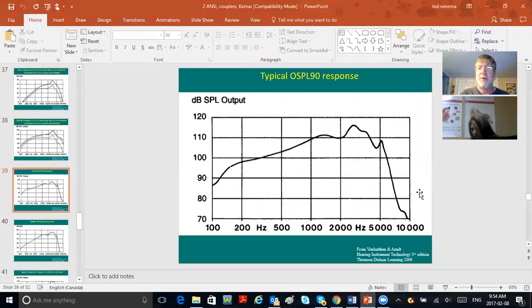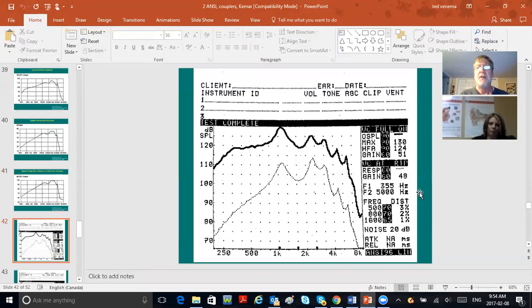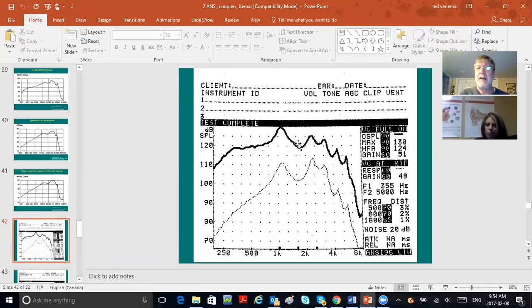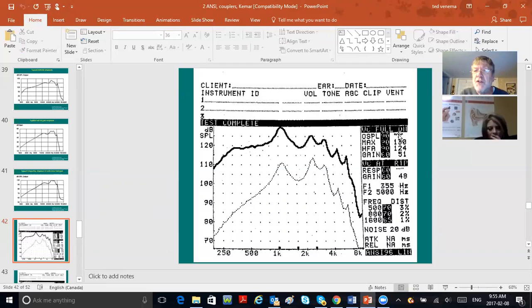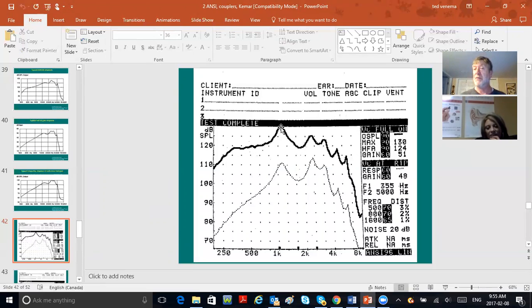Here's the OSPL 90 in black. Three things are shown: volume control full on; the OSPL 90 curve itself; and MAX—which stands for maximum—the peak, the highest point the hearing aid reaches, in this case 130 dB SPL.